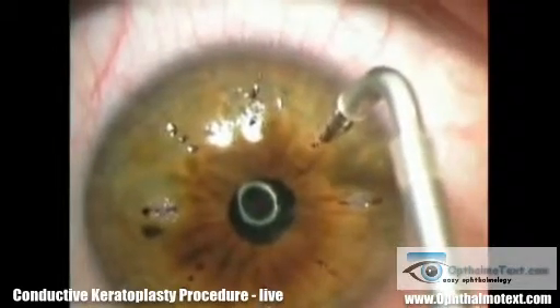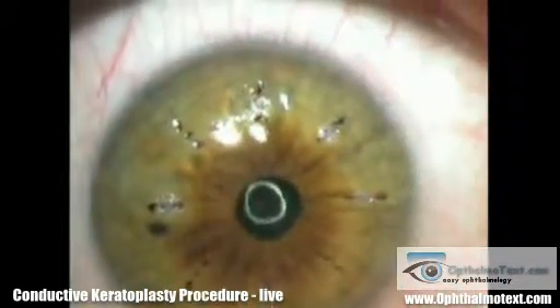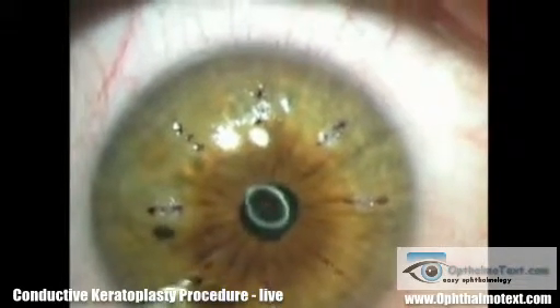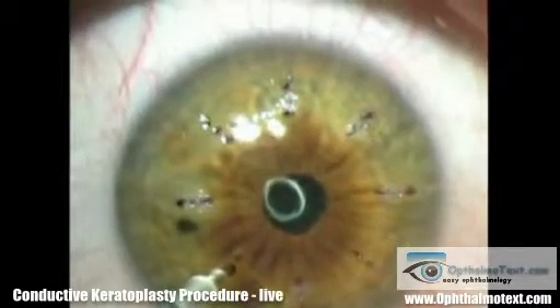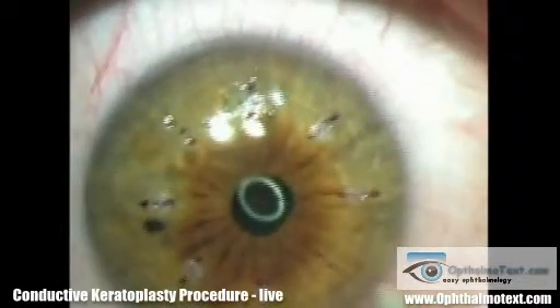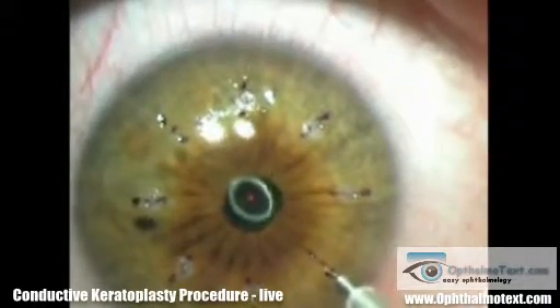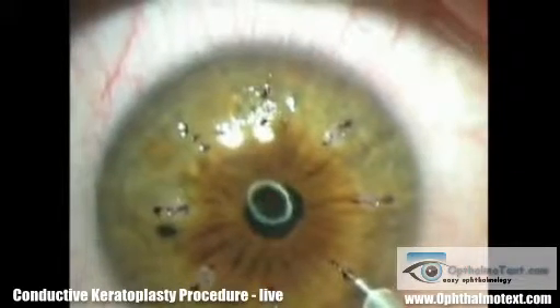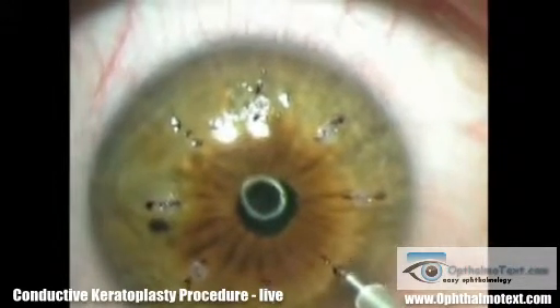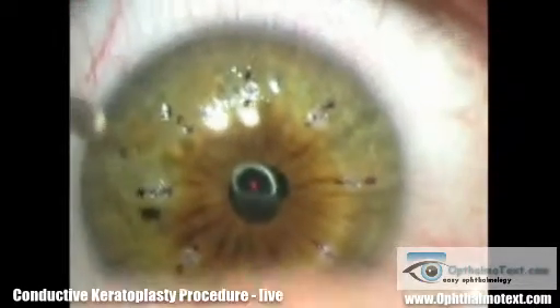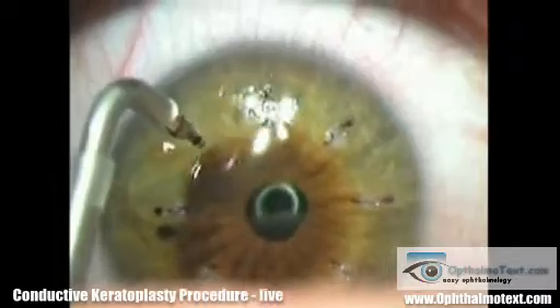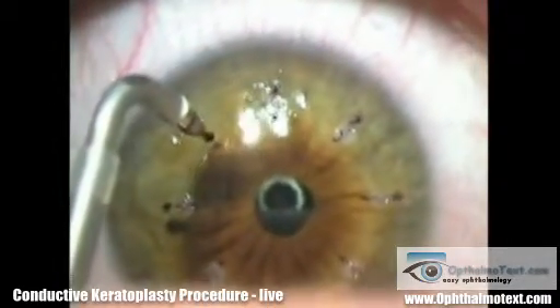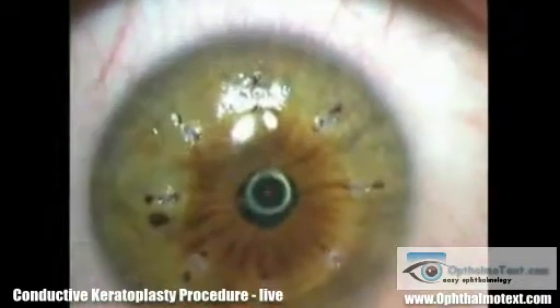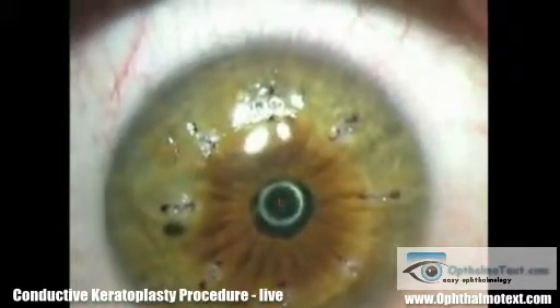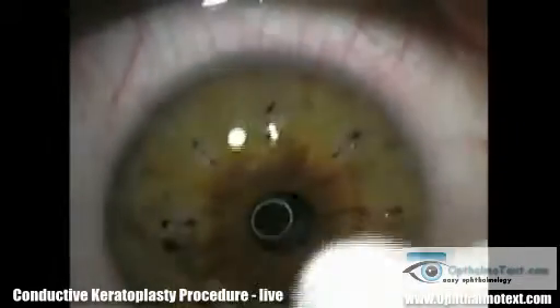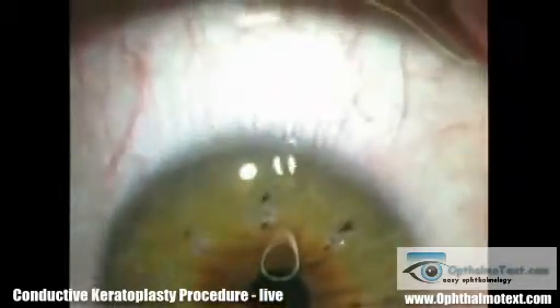It's important, which you'll begin to see now with the last 4 spots being placed, for the surgeon, as he's delivering the radiofrequency pulse, to watch the cornea very carefully. The corneal surface will usually contract away from the surgeon about halfway through the radiofrequency pulse, which lasts 0.6 seconds. As the cornea does contract away, it is very important for the surgeon to follow the retraction of the cornea with additional downward pressure of the tip. This allows the probe to remain fully seated throughout the entire delivery of the radiofrequency pulse.